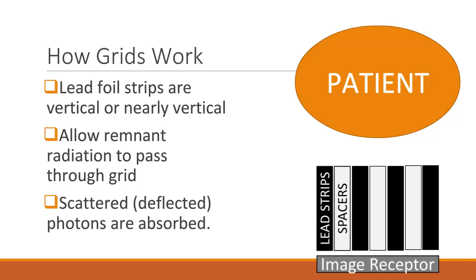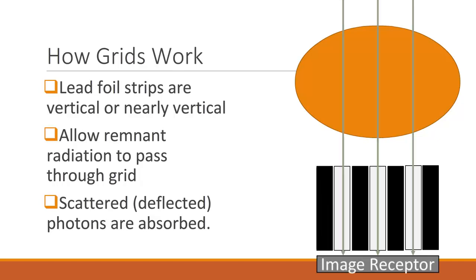The basic principle of how grids work is simple. The lead foil strips are vertical or nearly vertical to match the path in which the x-rays should travel to the image receptor. The radiolucent spacers allow the remnant x-rays — those that have passed through the patient — to reach the image receptor unobstructed, while the scattered x-ray photons, which have been deflected in all directions, are absorbed by the thin foil lead strips and prevented from reaching the image receptor and degrading the resulting image. Please note that the image here is not to scale and only meant to demonstrate the principle of how a grid works.